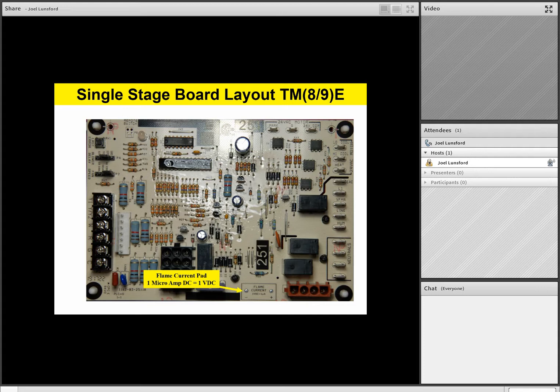But if we have a flame current that drops below 1.5 microamp DC, it'll start generating an amber flash code telling us that we have low flame current. And again, we'll talk more about that later when we get into flash code diagnostics. But just remember, 3.5 to 4 is a normal flame current.